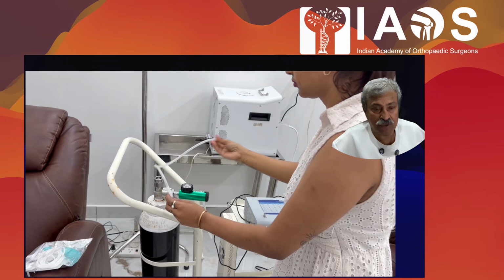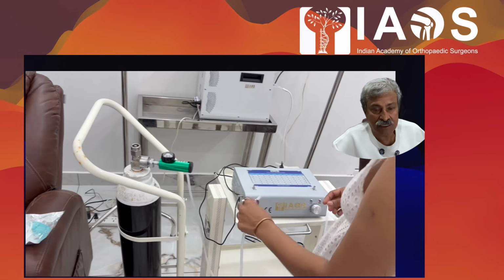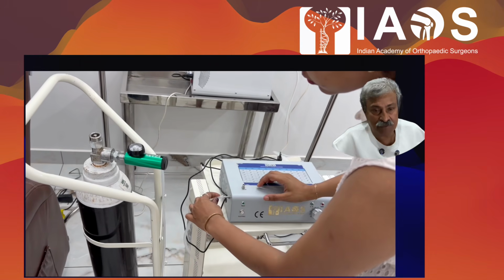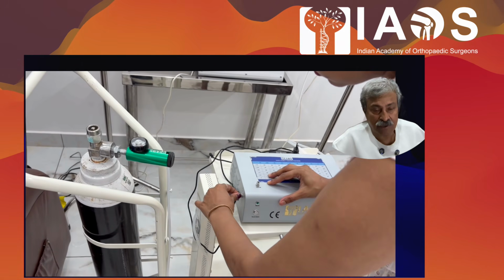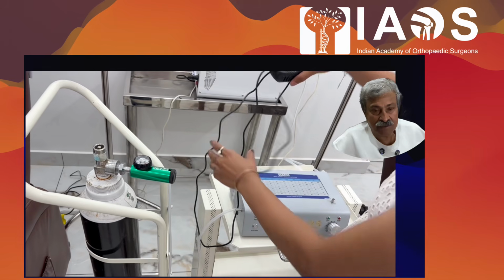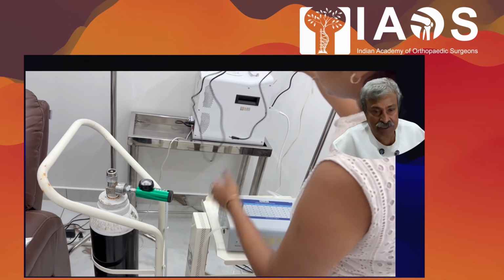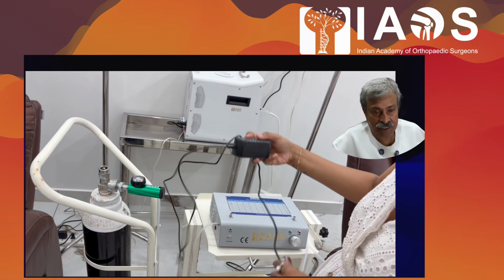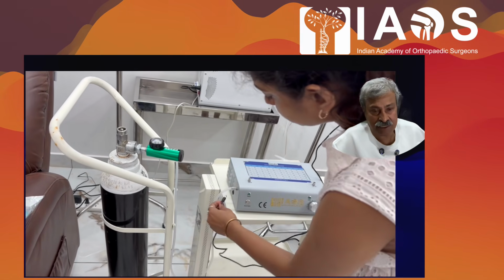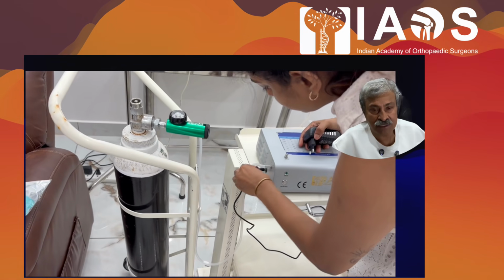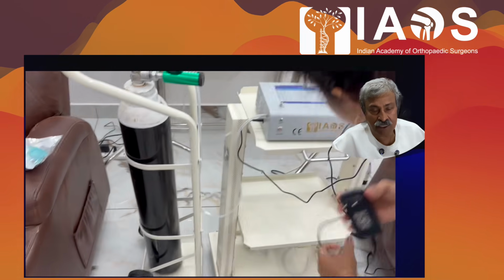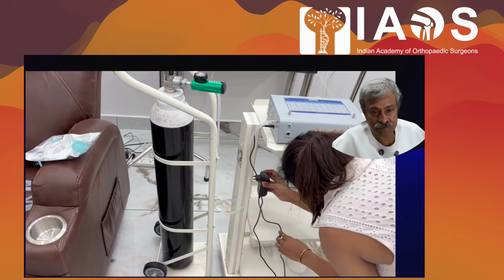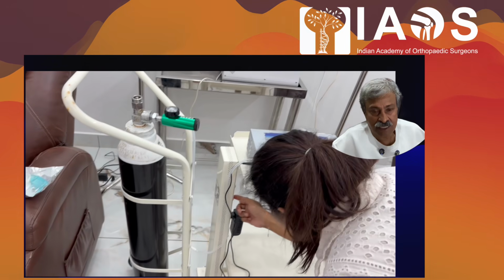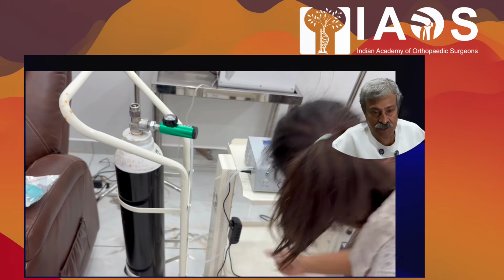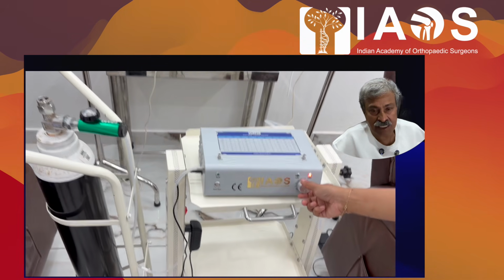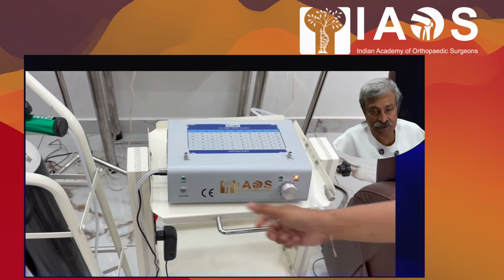The oxygen cylinder is connected with a pipe with a pressure regulating attachment. When accidentally the pressure of the cylinder becomes high, the machine is protected by the detacher. The power cord is plugged in, and once the switch is switched on, we can see the red light glowing, which shows that the machine is operational.